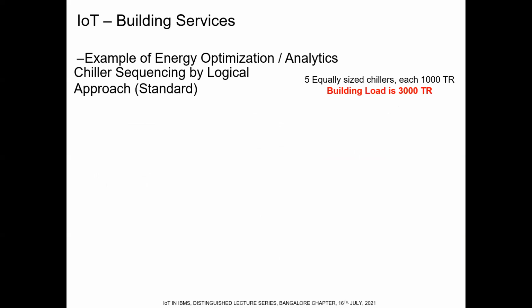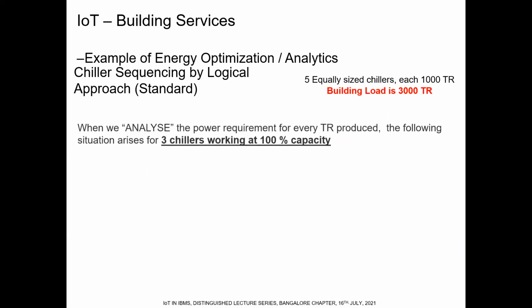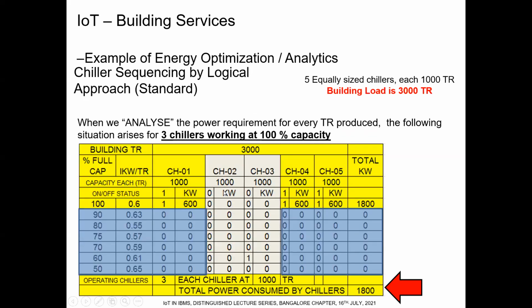Now we are going into the next step. Instead of doing the automation just based on capacity control, on the assumption that 3 chillers at 100% capacity will consume less power compared to 4 chillers at 75% capacity, without making that assumption, we are now trying to interact with the chiller vendor. That is the next step. The chiller vendor, in their catalog, has given this table. We are not looking at the table now.